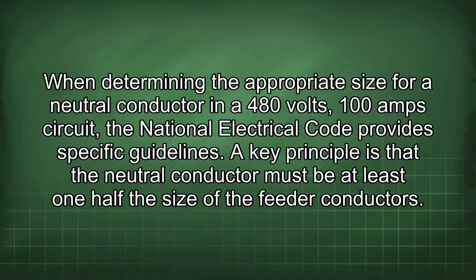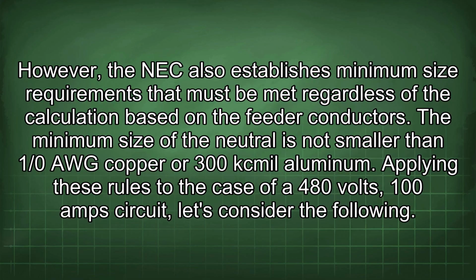When determining the appropriate size for a neutral conductor in a 480 volts, 100 amp circuit, the National Electrical Code provides specific guidelines. A key principle is that the neutral conductor must be at least one-half the size of the feeder conductors. However, the NEC also establishes minimum size requirements that must be met regardless of the calculation based on the feeder conductors. The minimum size of the neutral is not smaller than 1/0 AWG copper or 300 kcmil aluminum. Applying these rules to the case of a 480 volts, 100 amp circuit, let's consider the following.